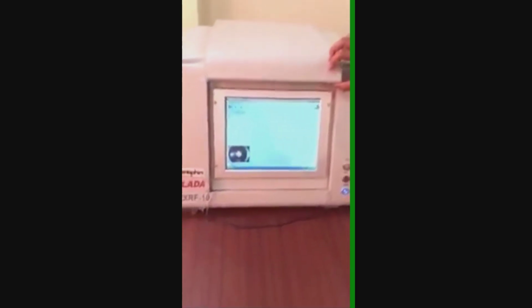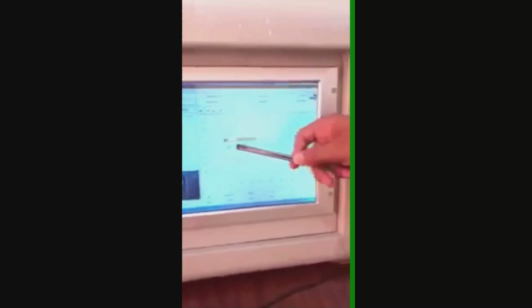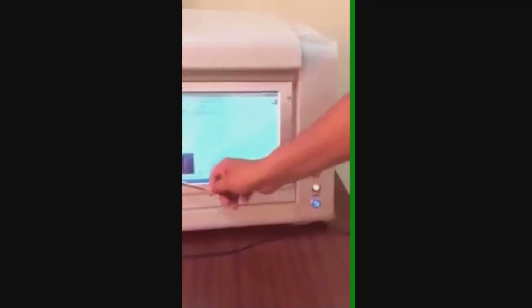Let's put the pure silver sample for calibration. By clicking the camera button, we can identify the placement of the sample on the testing window. Once it is done, we close the door and select the appropriate mode of testing. It is silver, so we select silver and click on the calibration button.